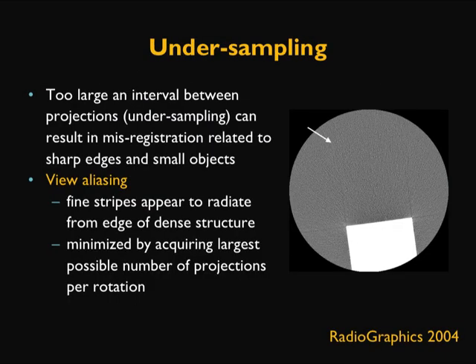A third type of physics-based artifact is under-sampling. Shown here is an image of a very dense object such as Teflon on a uniform surface. Under-sampling is caused when too large an interval between projections occurs, resulting in mis-registration related to sharp edges and small objects. As shown by the white arrow, streaks appear and are due to under-sampling of the projection data. This is called view aliasing, where fine stripes appear to radiate from the edge of a dense structure. This is minimized by increasing the number of projections per rotation.